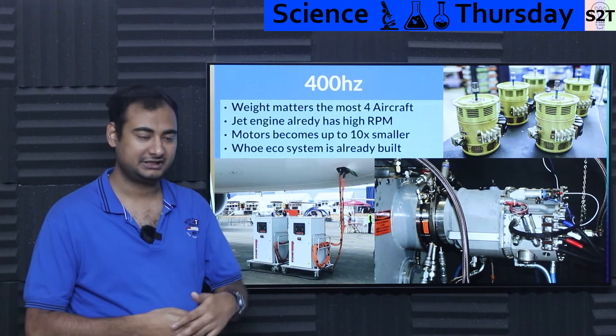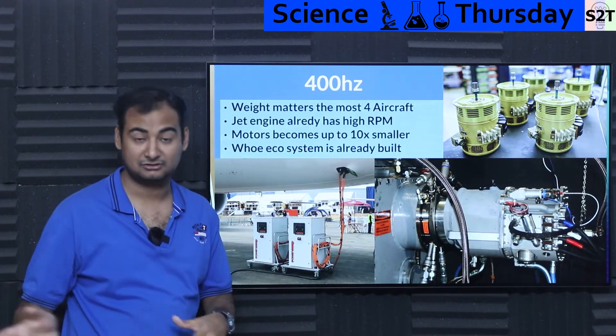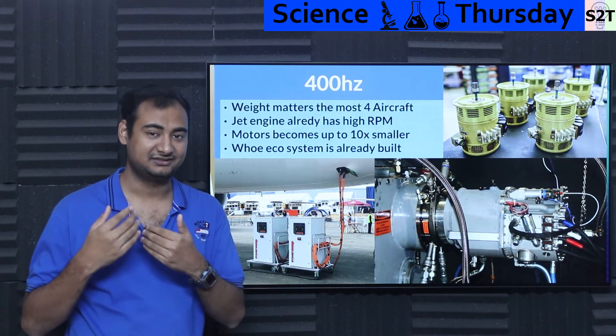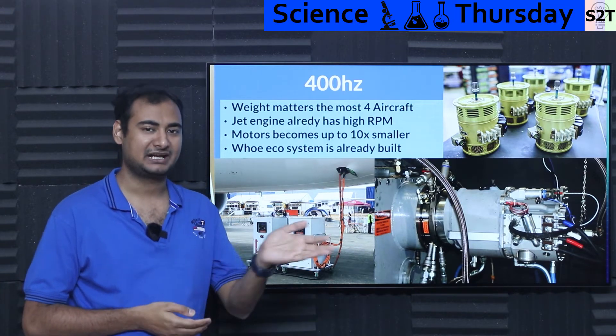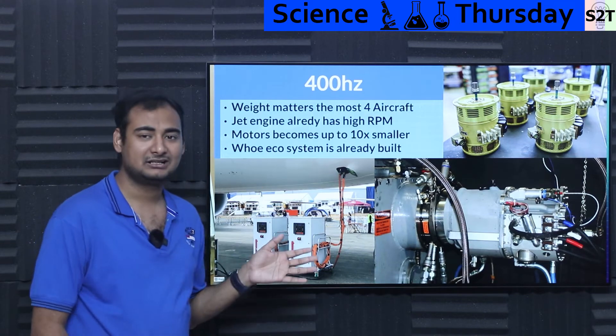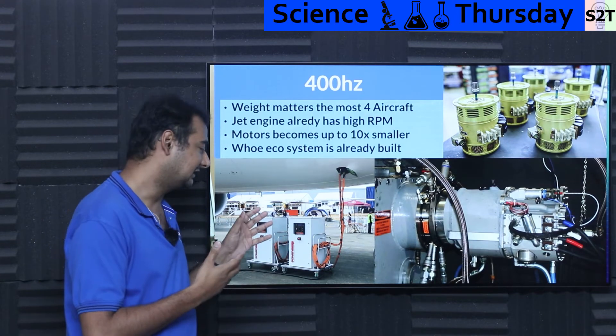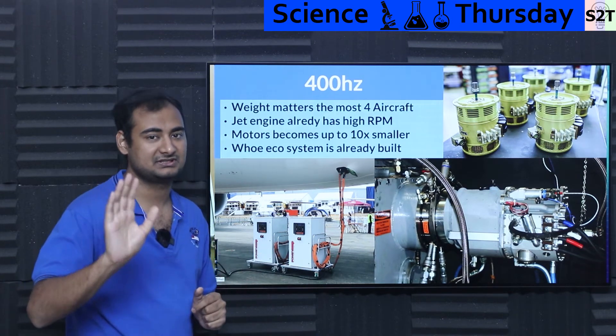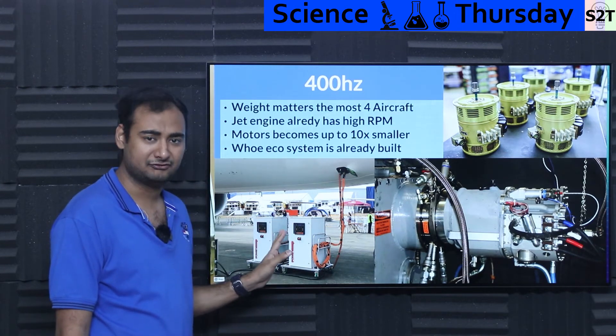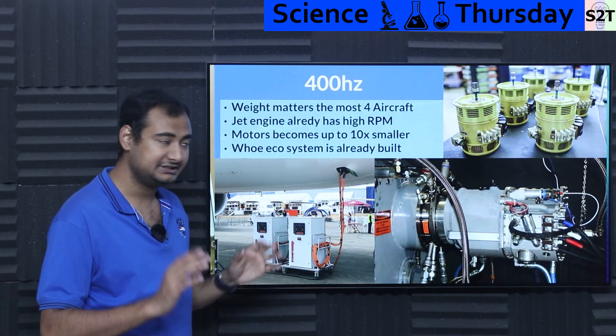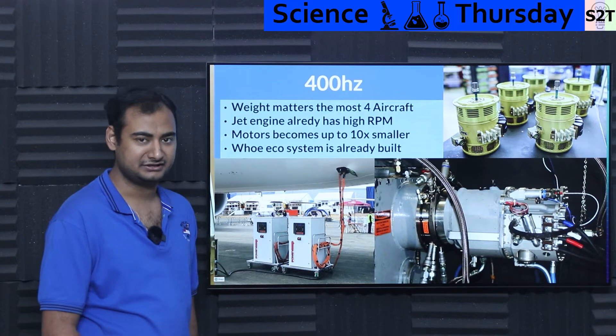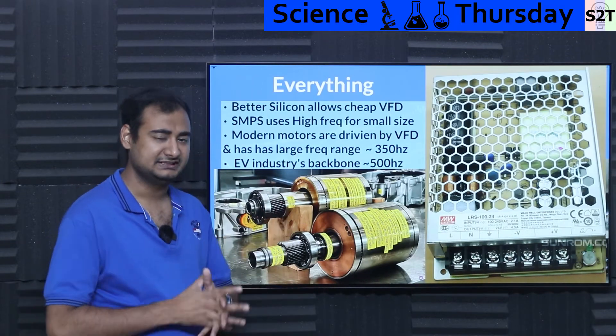Many airports will yoink a power supply into the aircraft and give you 400 Hz from a local source. In the old days that was a giant induction motor driving an AC induction generator — a mechanical frequency converter: 50 Hz or 60 Hz in, 400 Hz out. Nowadays you more commonly find a dedicated diesel generator creating 400 Hz power, or if you have good AC electricity, a VFD-style inverter that converts it and feeds it to the aircraft. It's a complete ecosystem with lots of suppliers and vendors — everything pre-done and pre-sorted.